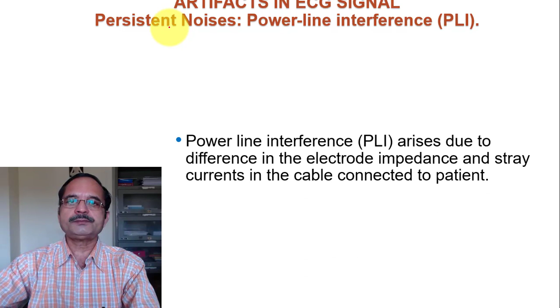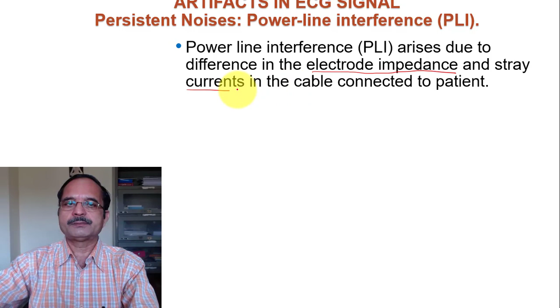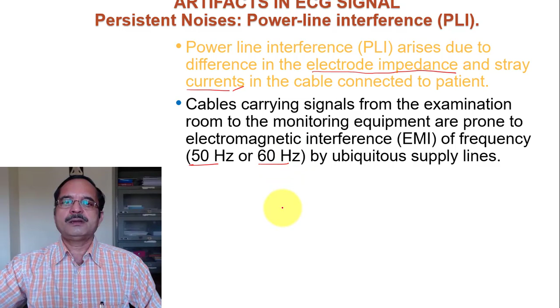The power line interference arises due to difference in the electrode impedance and stray currents in the cable connected to the patient. Cables carrying signals from the examination room to the monitoring equipment are prone to electromagnetic interference of frequency 50 Hz or 60 Hz depending upon the line frequency. This means the main reason for power line interference is the cables connected with the patient, because these cables are connected with equipment, and that equipment works on AC power supply, either 50 Hz or 60 Hz. Because of some reasons, this power line frequency gets superimposed on the ECG signal.